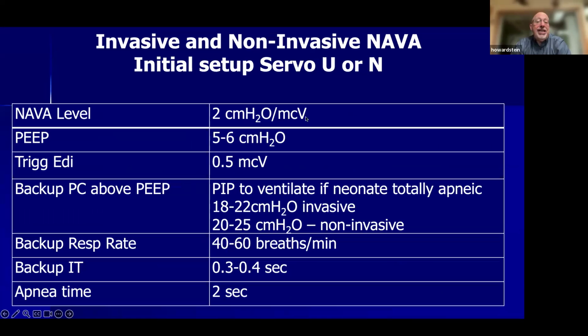So our initial settings, we suggest starting at a NAVA level of 2. I talked about the break point, and just having done well over 1,000 babies on NAVA now, I can tell you that 95% of them are very happy starting at a NAVA level of 2. Occasionally, it's a little bit too much and you have to back off, and occasionally it's not enough and you have to go up, but the majority are happy with 2. PEEP, whatever you use in your unit, approach it the same way. Your EDI trigger at 0.5, that's the factory setting, stay with that. And then your backup support, you just want to pick pressure to ventilate if the baby's apneic, so 18 to 22 roughly for invasive and a little higher for non-invasive.